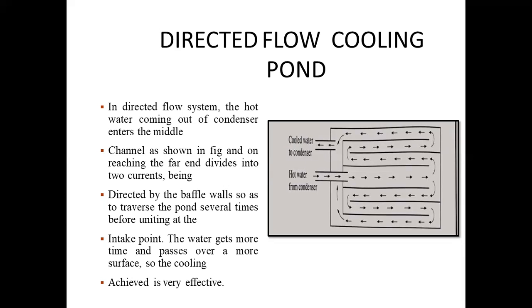In case of directed flow cooling pond, you can say that hot water is supplied from here. These plates are of metallic. Hot water supplied from here. This hot water is distributed in two sides, and then this flow is directed. These plates are mostly of metal, so that water can release its heat, and cold water can be collected from here. In directed flow system, the hot water coming out of condenser enters the middle channel as shown in figure, on reaching the far end, divides into two currents being directed by baffles so as to traverse the pond several times before uniting at the intake point. The water gets more time and passes over a more surface, so cooling achieved is very much effective.